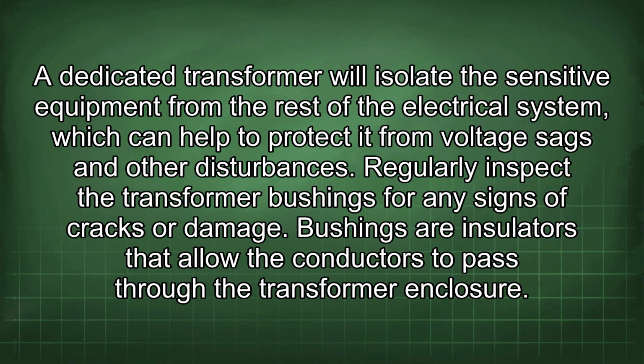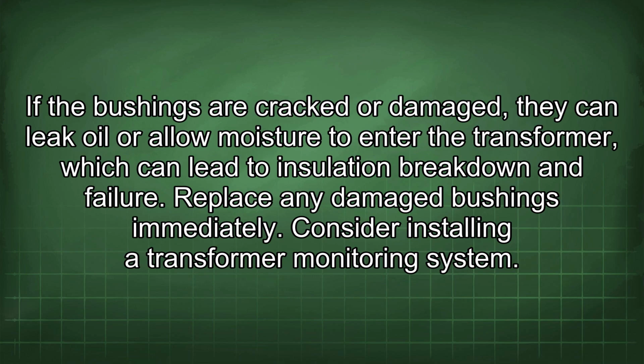Regularly inspect the transformer bushings for any signs of cracks or damage. Bushings are insulators that allow the conductors to pass through the transformer enclosure. If the bushings are cracked or damaged, they can leak oil or allow moisture to enter the transformer, which can lead to insulation breakdown and failure. Replace any damaged bushings immediately.